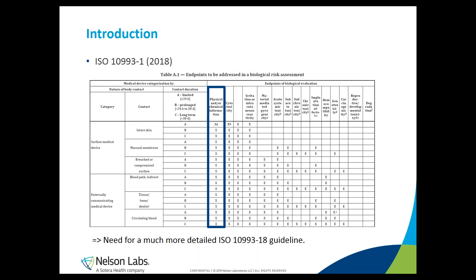Yes, of course, Annelies. It all started with the release of the new ISO 10993-1 in 2018, which stated that getting chemical information from your medical device is the first preliminary stage in any biological evaluation. However, the current ISO 10993-18 from 2005 was not detailed enough to allow a proper assessment of your medical device. Therefore, there was a clear need for a new guideline summarizing the state-of-the-art approach to performing chemical characterization to evaluate the final safety of your medical device.